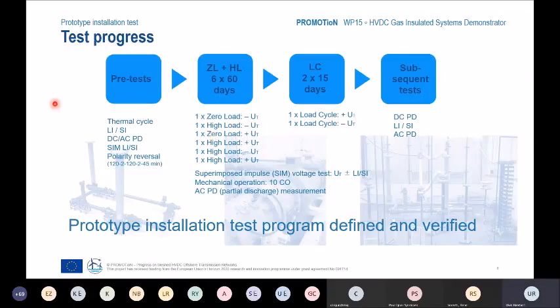The next slide shows the test procedure for this long-term test. If you look at these test procedures, then you can see some similarities to a test well known from cable as a pre-qualification test. But the idea behind the pre-qualification test for cable is different to that of what we have developed for GIS. For cable, that means mainly aging of the polymeric material and mechanical stress due to different thermal situations. For a GIS, it's known from the AC side that the aging is not a real issue for the GIS and for the gas itself. Therefore, we have focused on covering most of the different typical situations during real operation.